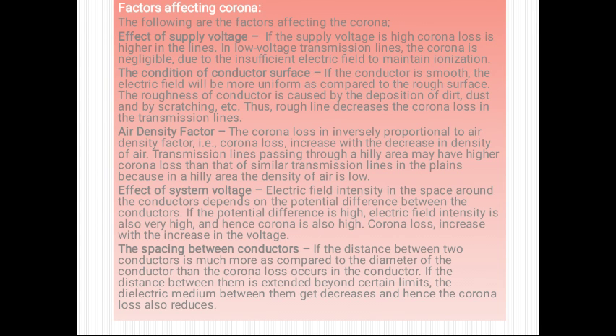Next is spacing between the conductors. If the distance between two conductors is not much more as compared to the diameter of the conductor, then corona loss occurs in the conductor. If the distance between them is extended beyond certain limits, the dielectric stress between them gets decreased and corona loss is also reduced. It means if conductors are placed at a proper distance in which there is no ionization or no effect of electric field on the other conductor, then corona loss reduces.